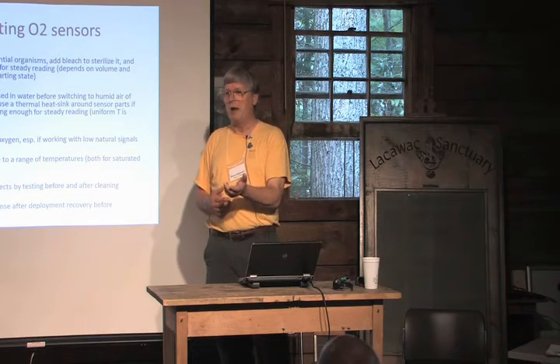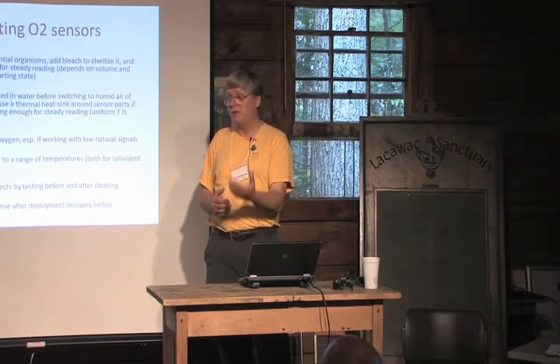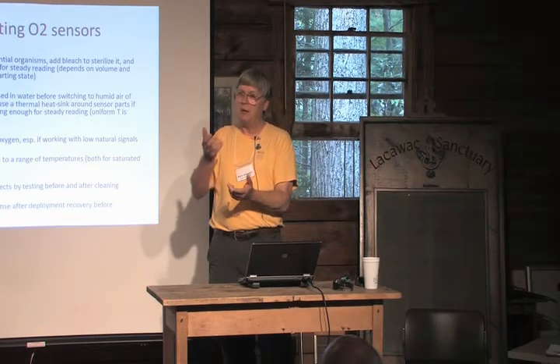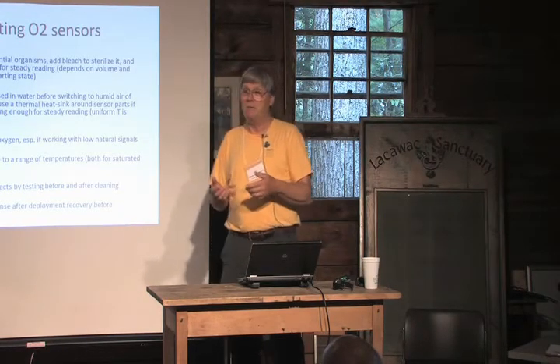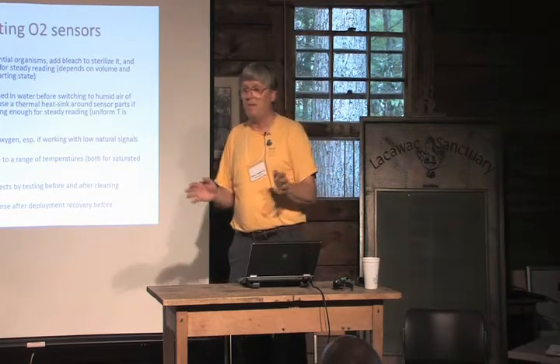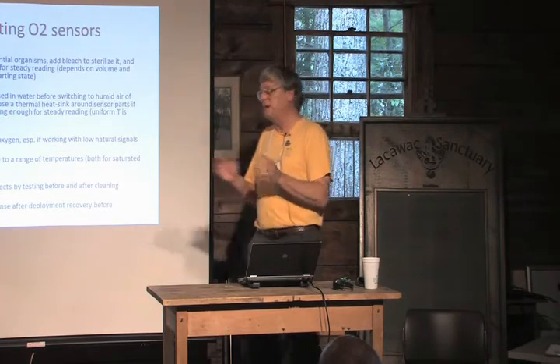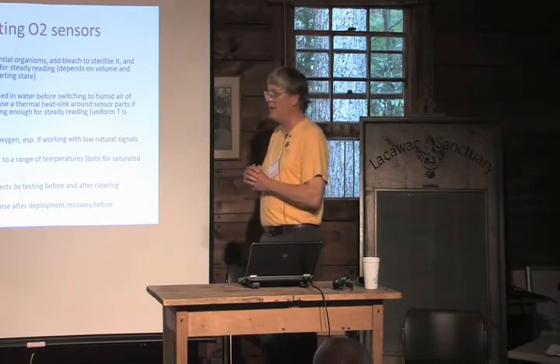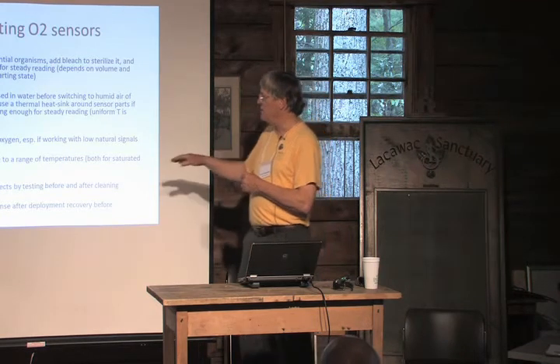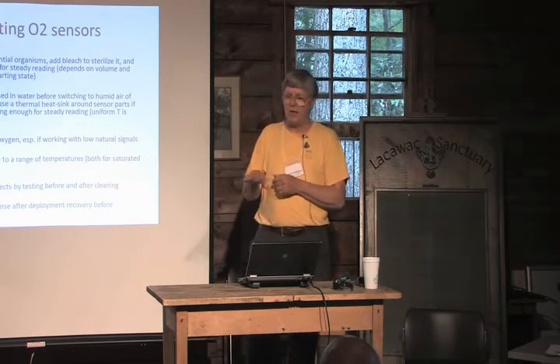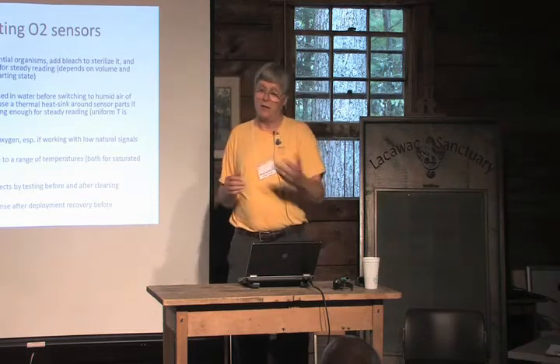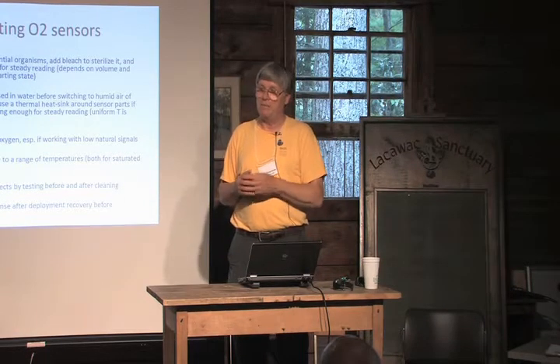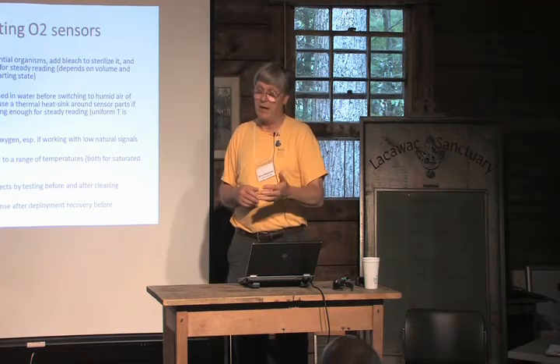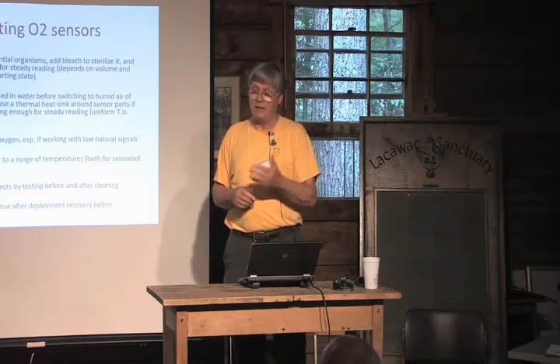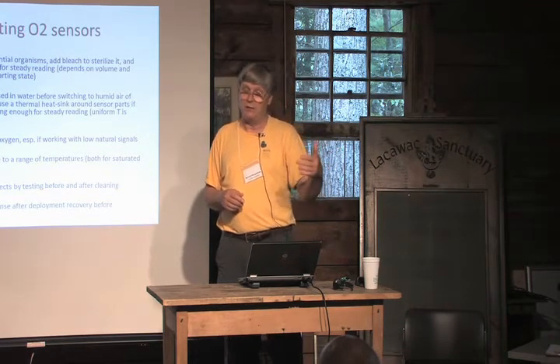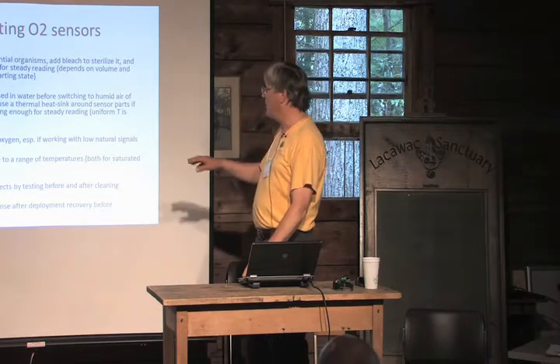Measure its response for a while under standard conditions, then clean it and measure it again. And if the signal goes up a little bit or down a little bit, then obviously cleaning had an effect. If it's a very small effect, you can pretty well assume that biofilm effects are minimal. The very best way is to put it in a small volume of water with no mixing and repeat that test, uncleaned and cleaned. And you may be able, if the temperature is right, to actually recreate the magnitude of the effect in the lake before you retrieved it and then correct for it that way. I can talk more about that later.